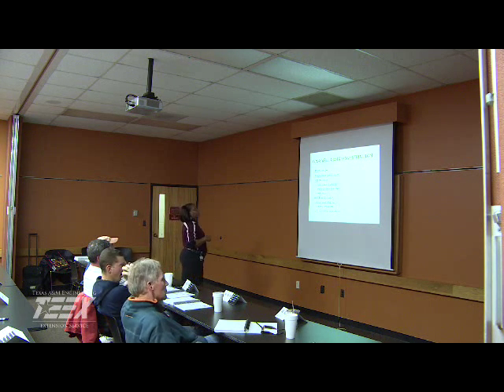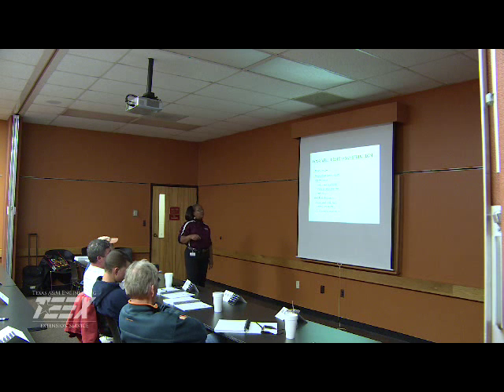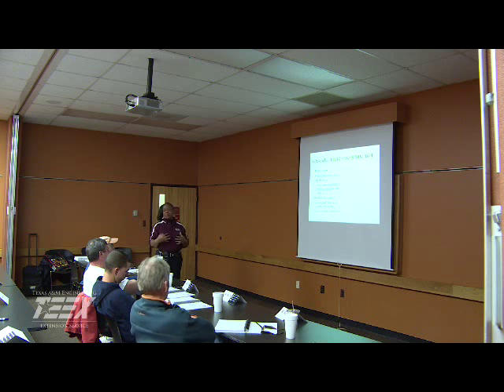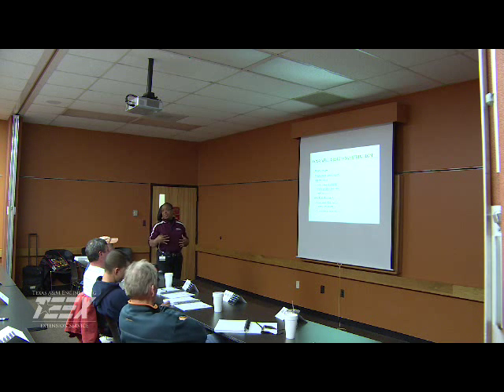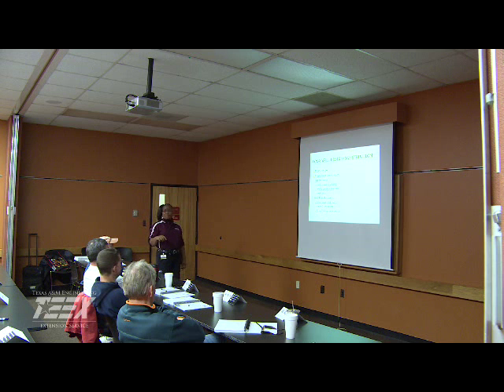When I have poor design or construction, again, it could be based on overpumping. Do I have too many wells that were in their circle of influence or radius of influence overlap? Because all of that can also create the issues that we were just talking about. What about with the well development? Did we remove the drilling mud? If not, that could be an issue.